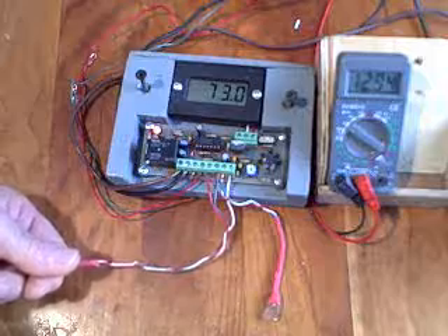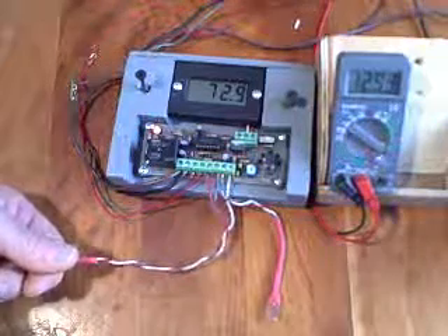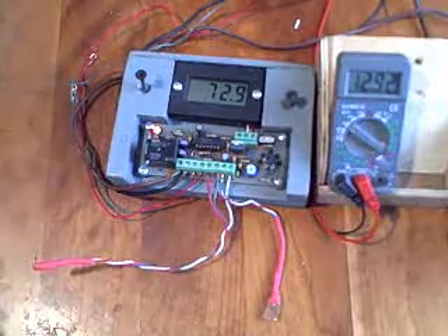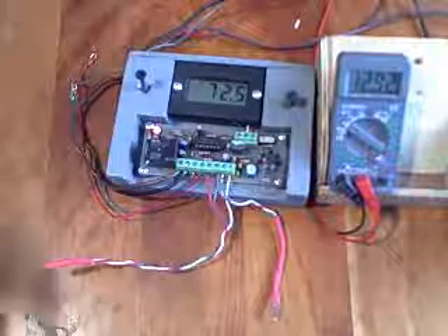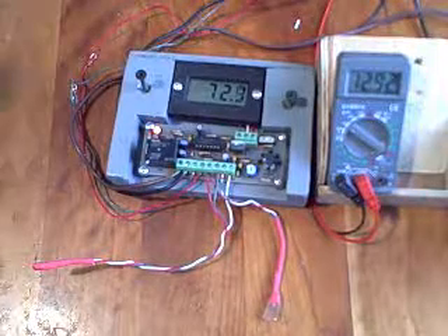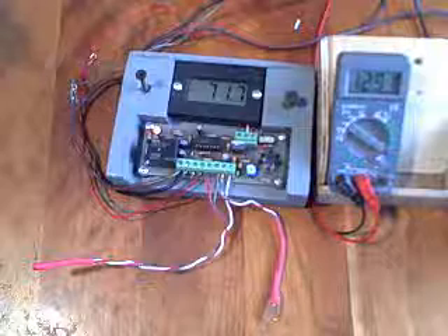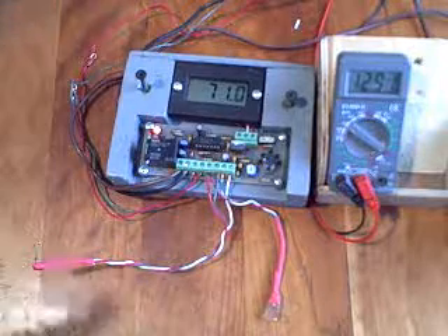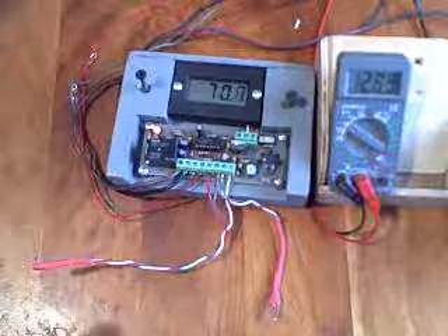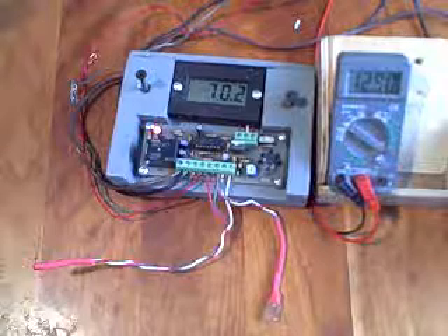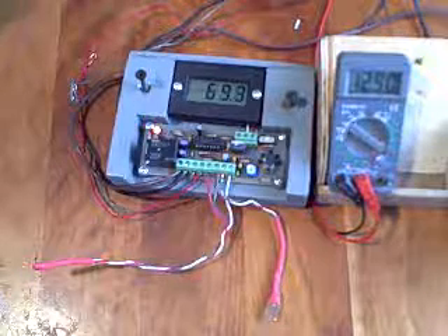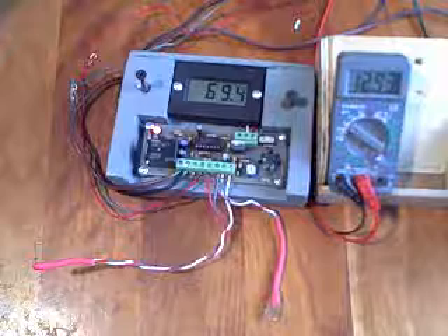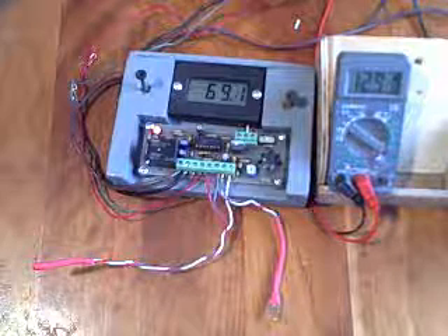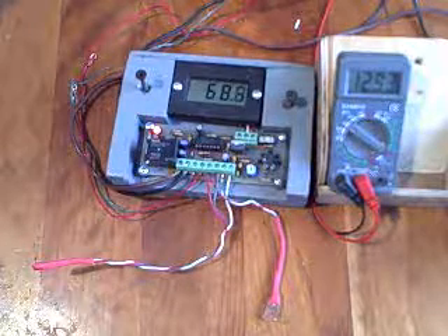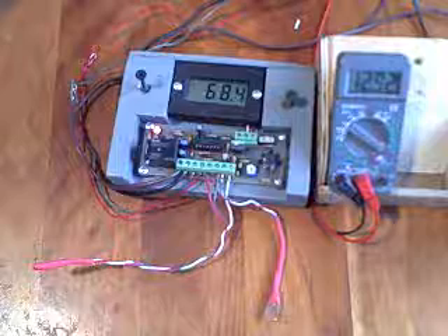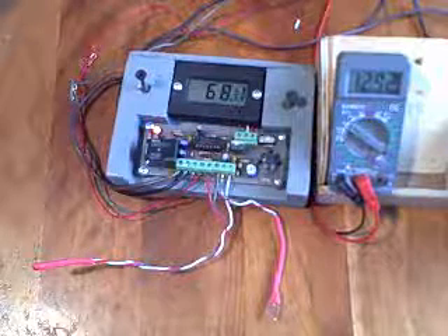Okay, so I'm going to release the probe now, and we'll let the temperature cool down, and we'll see how long it takes to turn the pump off. Now, we don't want the pump to go off right away, even though the temperature is going down. If that happened, the pump would be going on and off all the time, and it would wear out the pump. Every time this pump starts, it's a bit of a shock.